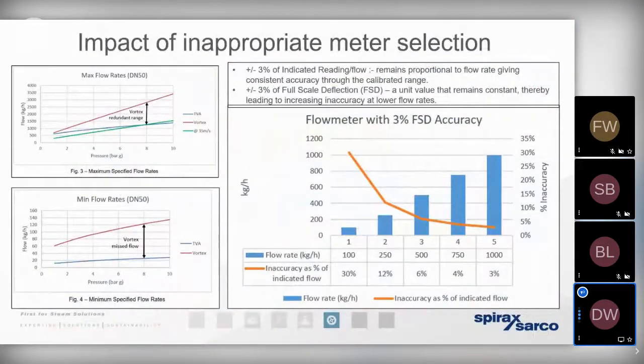So with regards to accuracy, it's important to understand that different manufacturers will quote accuracy in different ways, and this can be really misleading. So if we look at FSD, that's full scale deflection. Let's say we had a flow meter that was passing 1,000 kilograms per hour of steam at 100% capacity, and it was quoted as having a 3% full scale deflection accuracy. Then that could mean that there was 30 kilograms per hour of steam that was not being read by the meter.